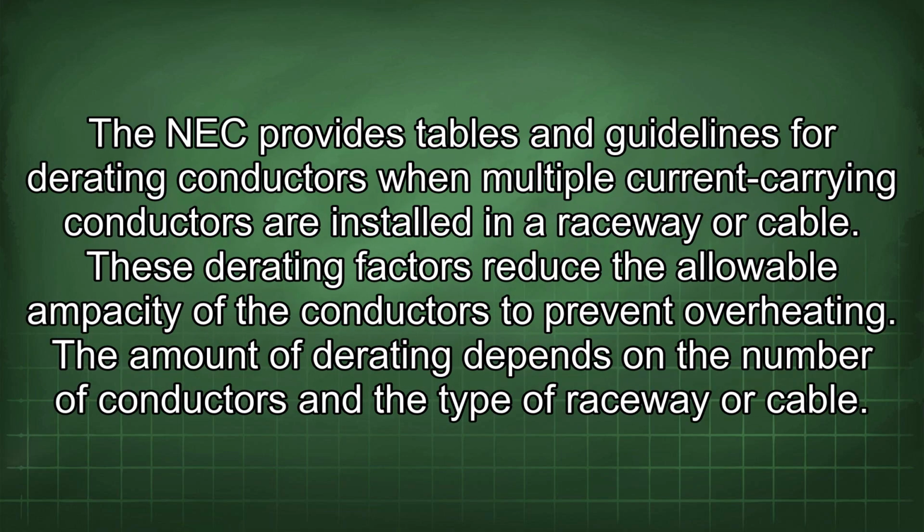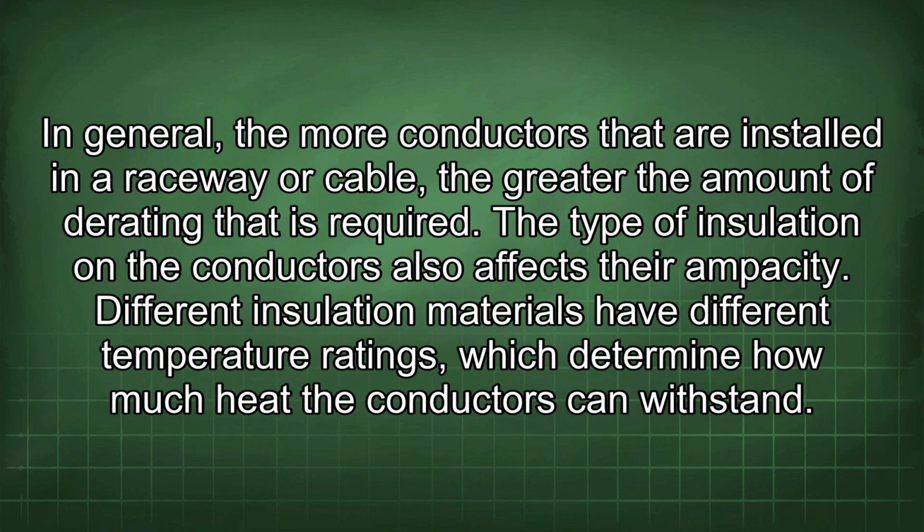The NEC provides tables and guidelines for derating conductors when multiple current-carrying conductors are installed in a raceway or cable. These derating factors reduce the allowable ampacity of the conductors to prevent overheating. The amount of derating depends on the number of conductors and the type of raceway or cable. In general, the more conductors that are installed in a raceway or cable, the greater the amount of derating that is required. The type of insulation on the conductors also affects their ampacity.